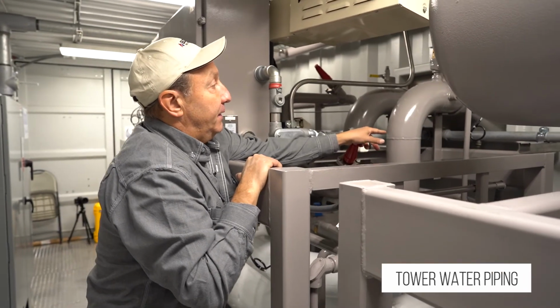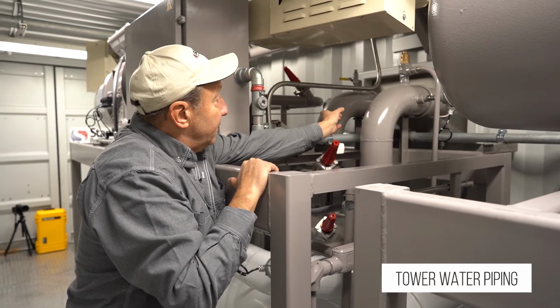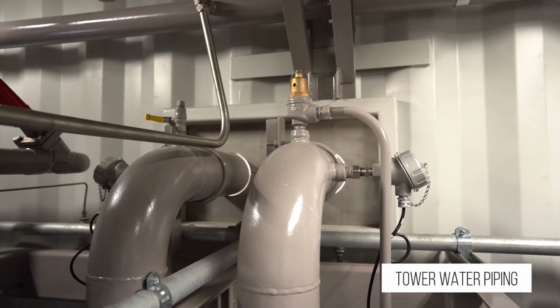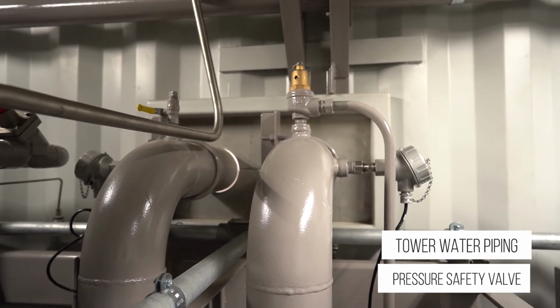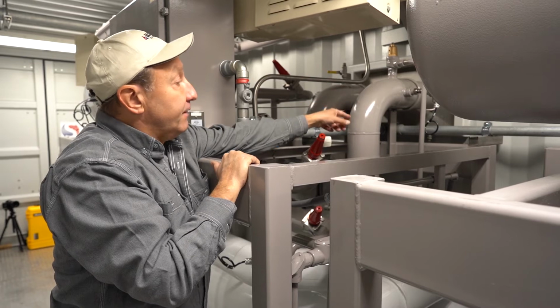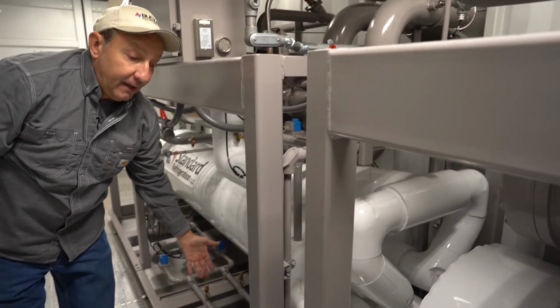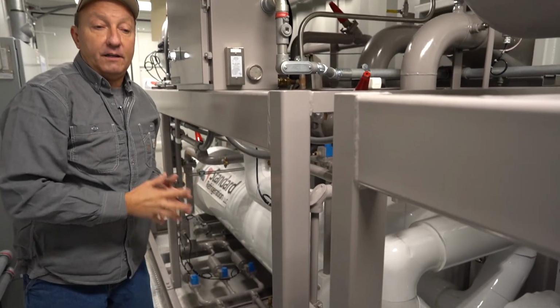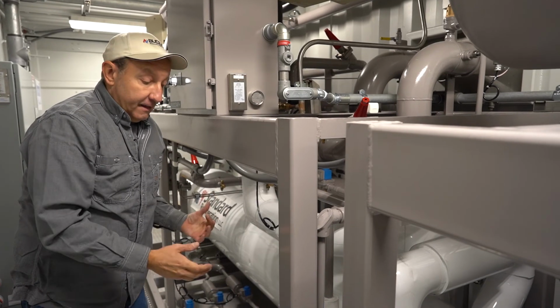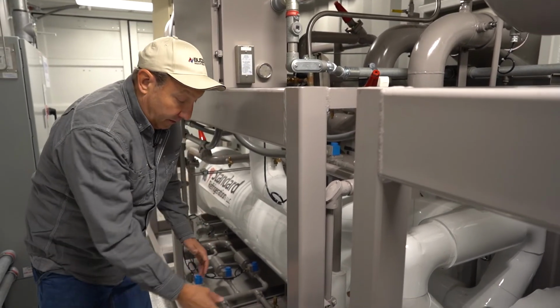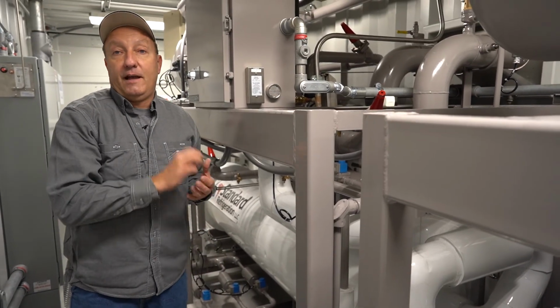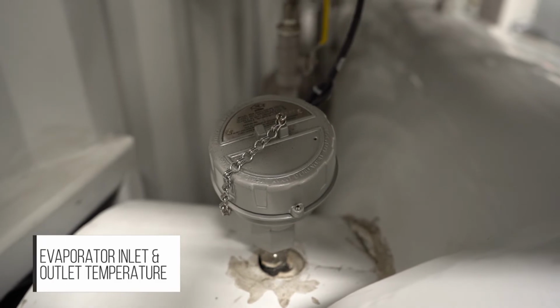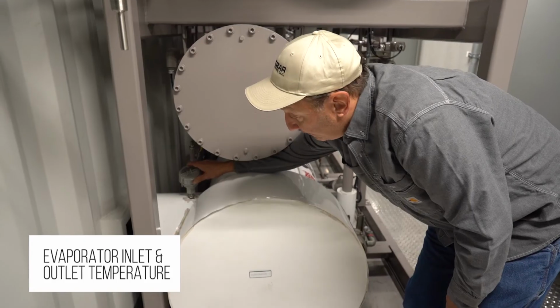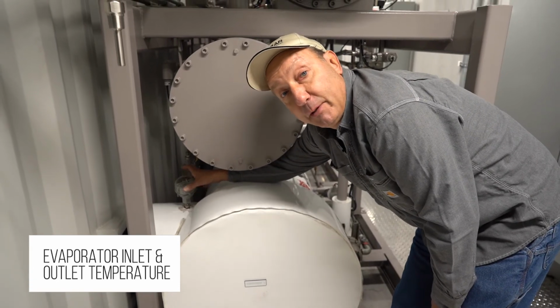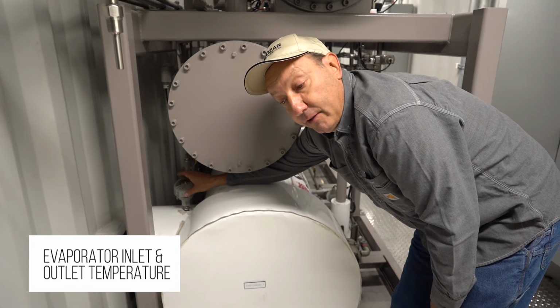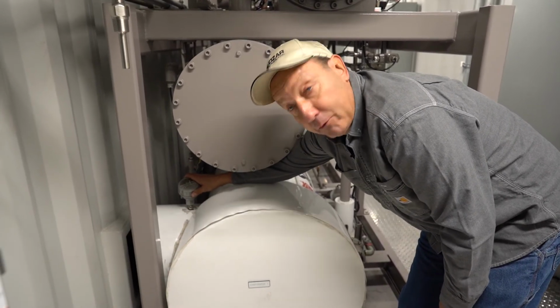Okay, this is our tower water piping. We monitor temperature in and out, PT100 RTDs. It's also protected by a 150 PSI pressure safety valve, PSV. If that was ever to release, it has a blow down tube and goes to our stainless steel drip pans. The entire chiller, each circuit, each chiller is self-contained, and in the event of a glycol leak or a tower water leak, it collects in the drip pans in the bottom, and at the end of the drip pan there's a 1/2-inch drain connection. We also monitor evaporator inlet and outlet temperature, again with a PT100 RTD in a thermal well, so they can be removed and taken out for calibration or replacement or service without draining the system.